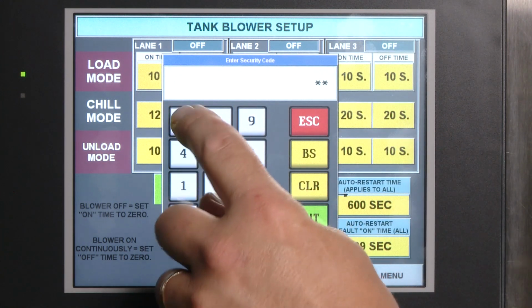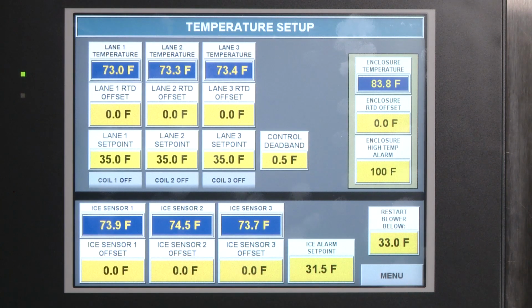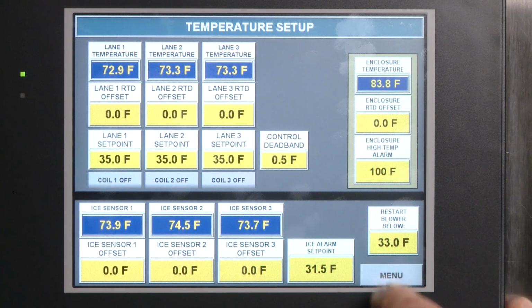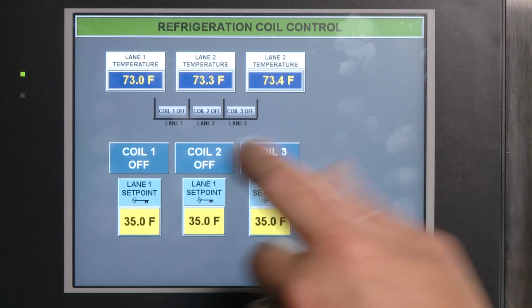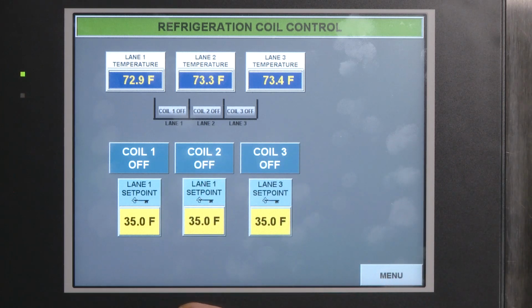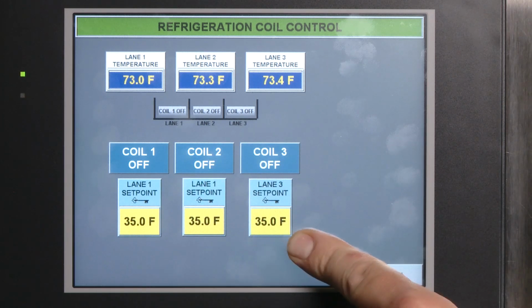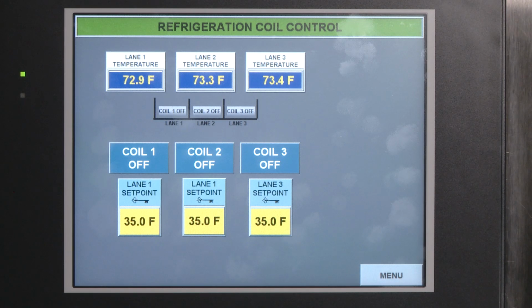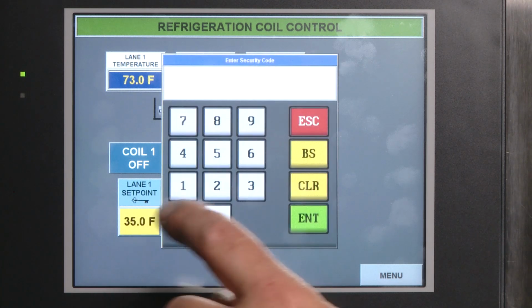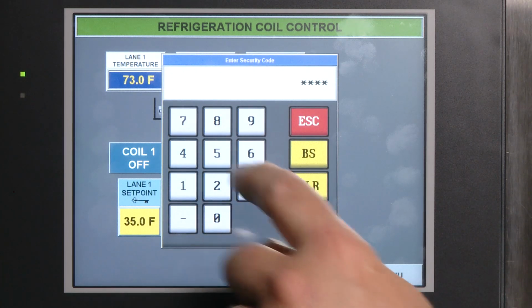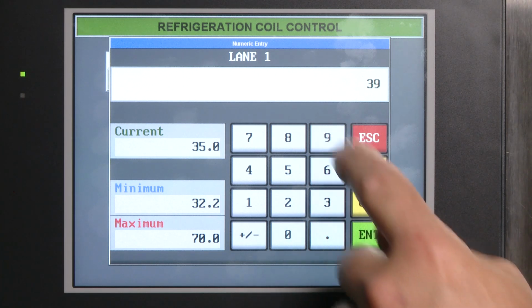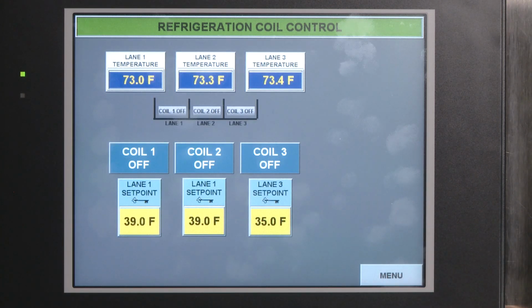Now let's navigate to the temperature setup screen to display the controls for temperature. Temperature control is accomplished by cycling the refrigeration valves on and off. Temperature control set point is set by pressing the lane set point displays. A password is required to change any values on this screen. When the security keypad pops up, enter your password. After the password is entered, you may change the value.